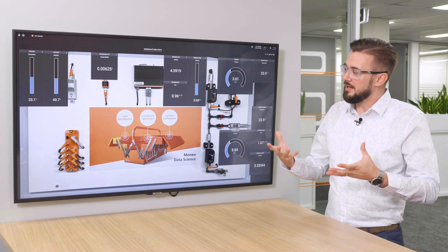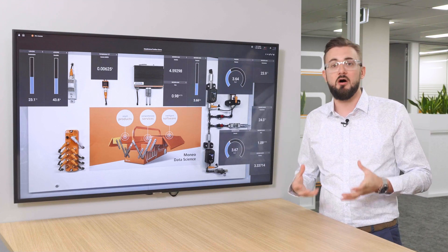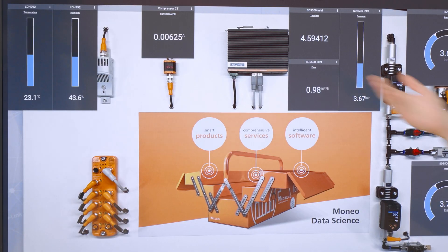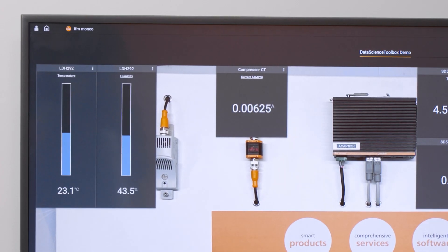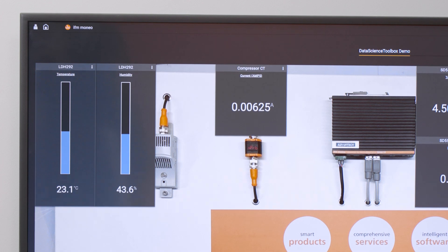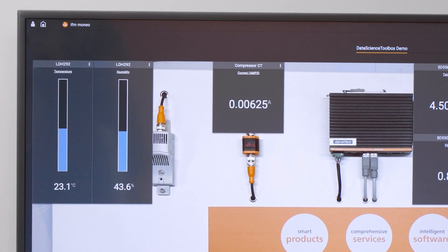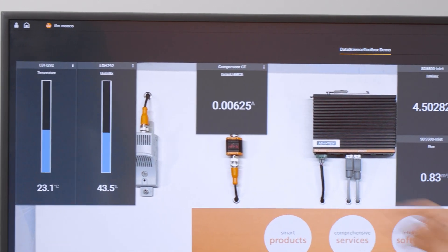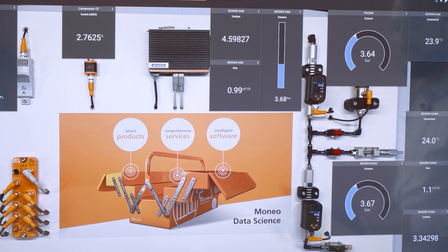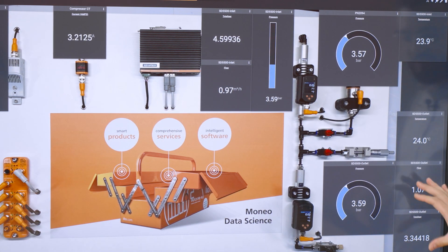To gain a little more understanding of what we're trying to achieve — you're really trying to see how hard the compressor is working. We have an extra sensor deployed to detect humidity inside the compressor room, as well as temperature, and a current transmitter to see how hard the compressor is working. The IPC I explained earlier also monitors system pressure to make sure it's pressurized, and more importantly, we've got the inlet flow and the outlet flow.